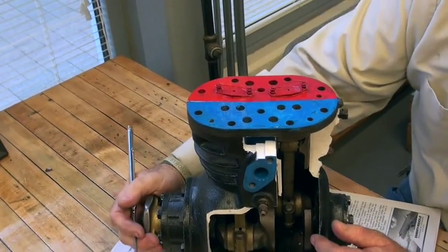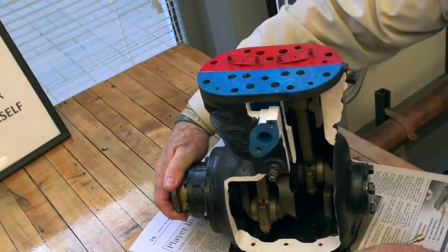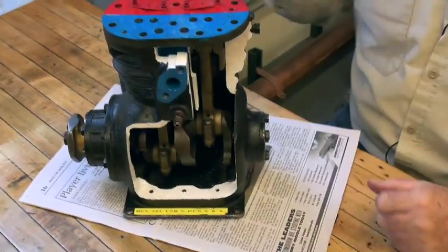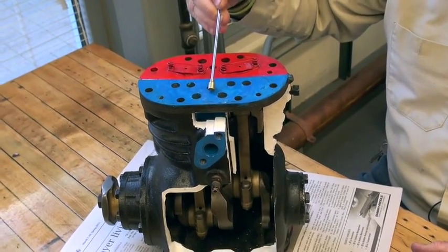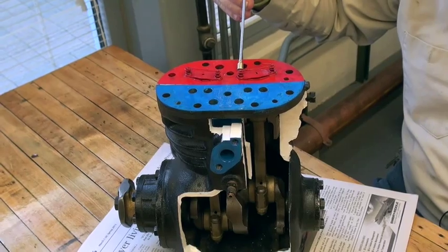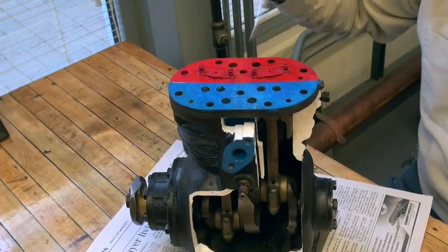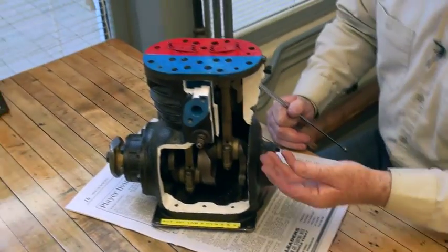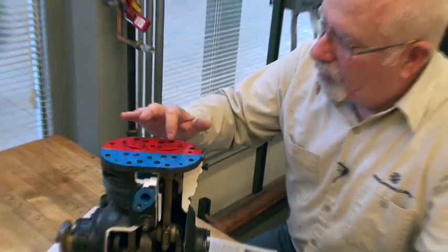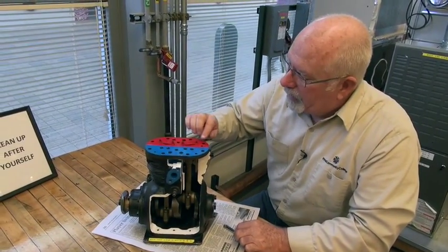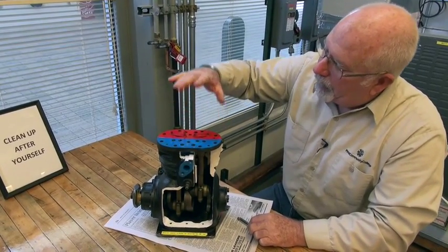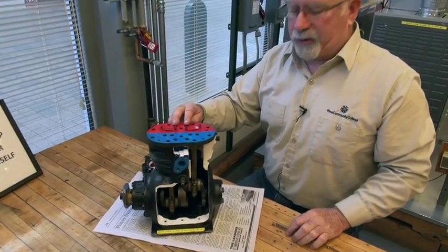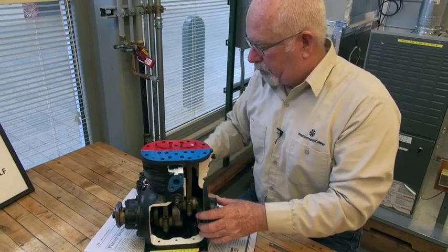So as that piston comes up to dead top center, it's compressed it now from a low pressure, low temperature, superheated gas to now a high pressure, high temperature, superheated gas. All right? Just because it was all vapor and it's compressed it now so that whatever this was set at pressure-wise, it's going to open it up and allow the high pressure, high temperature, superheated gas to come into this side of the compressor, excuse me.